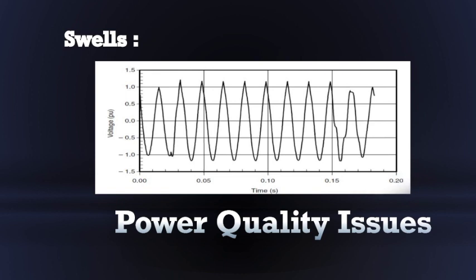You can see the figure. In this figure, voltage swell is caused by a single line to ground fault. You can see a rise in the voltage from 1 per unit, which indicates swell. The same kind of waveform can also occur by switching off a large load or energizing a large capacitor bank.